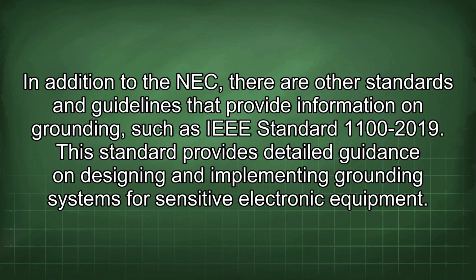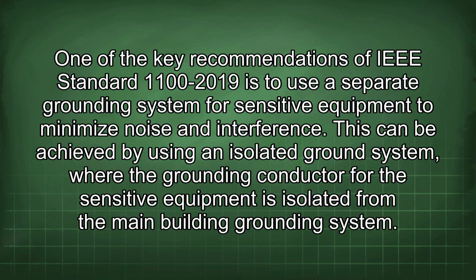In addition to the NEC, there are other standards and guidelines that provide information on grounding, such as IEEE Standard 1100-2019. This standard provides detailed guidance on designing and implementing grounding systems for sensitive electronic equipment. One of the key recommendations of IEEE Standard 1100-2019 is to use a separate grounding system for sensitive equipment to minimize noise and interference. This can be achieved by using an isolated ground system, where the grounding conductor for the sensitive equipment is isolated from the main building grounding system.